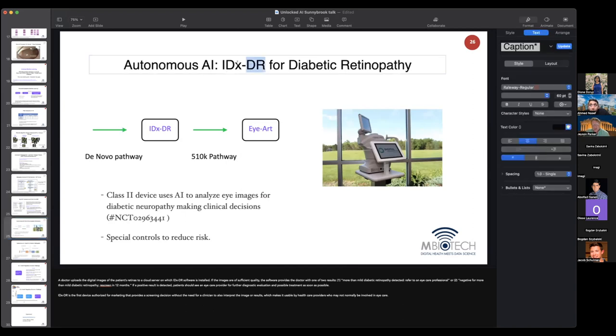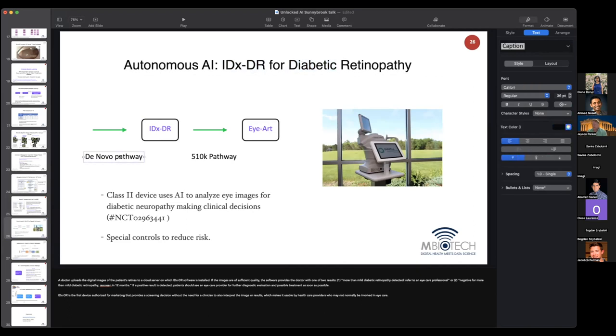The IDx-DR system is one of several recent approvals using AI — in this case a neural network — for diabetic retinopathy. The original IDx-DR system was approved by the de novo pathway. De novo and 510-K submissions usually don't have a lot of clinical data, but these submissions have a lot — which is great to see. There's also a lot of disclosure, which may seem strange because when it comes to medical device submissions, there's typically not much. Medical device disclosure is nowhere near what it is for drugs. Good to see sample sizes. Good to see clinical data.